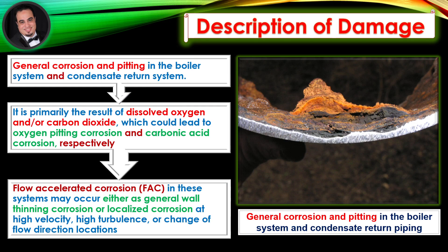Description of damage. General corrosion and pitting in the boiler system and condensate return system, as shown in figure. It is primarily the result of dissolved oxygen and/or carbon dioxide, which could lead to oxygen pitting corrosion and carbonic acid corrosion, respectively.